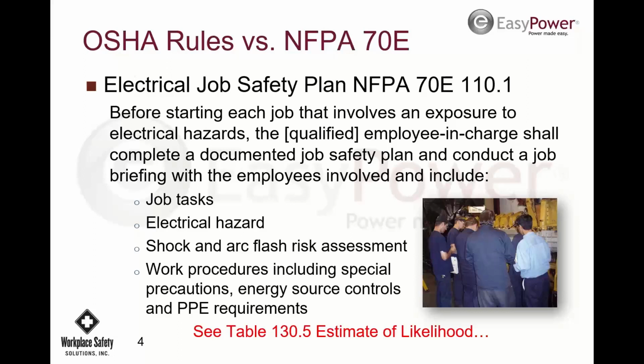The other thing I see companies do is have an arc flash study done, and we may find some breakers or equipment that's over dutied. It's not rated for the fault current anymore, and that's a pretty serious situation that can impact the arc flash level. They think they'll put on the stickers we provide and they're done. But in reality that's not the case, because they probably should be replacing equipment that is not rated for the fault current. It's a liability thing people need to be aware of: once it's in writing that you've got this issue and you don't address it, that's something to consider as you go forward.